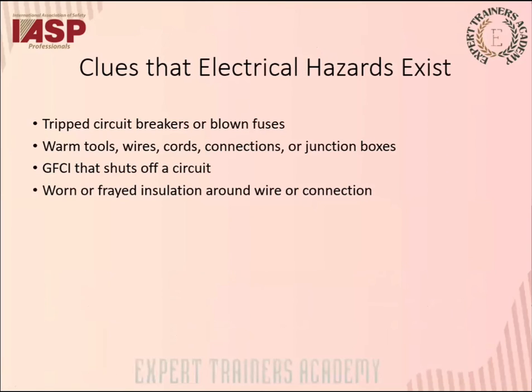What are the clues? How to identify that electrical hazards exist in your building or in the workplace? Frequent tripped circuit breakers or blown fuses. Tools become warm quickly. The wires become warm quickly. The cord or the cables or the connection, the junction boxes get overheated. The GFCI, the ground fault circuit interrupter, shuts off a circuit very frequently. There's worn or frayed insulation around wire or connection. So the insulation gets broken off from the wire or the connection. So these are the things that we can identify. Yes, there is an electrical hazard in the building or in the workplace.